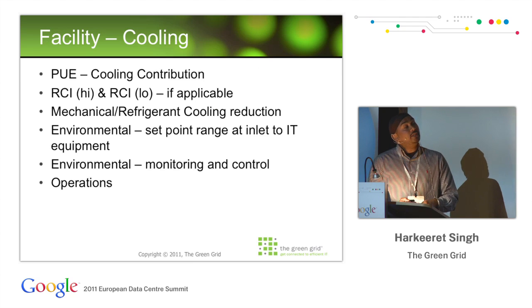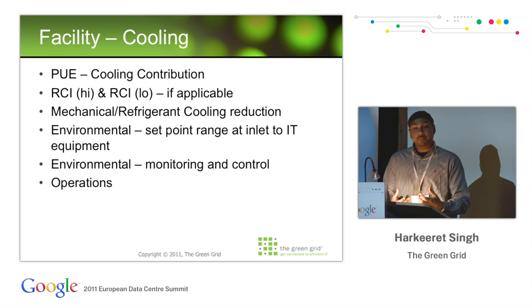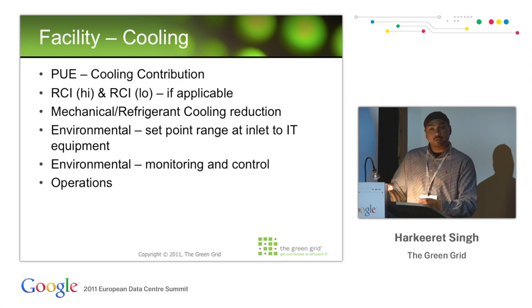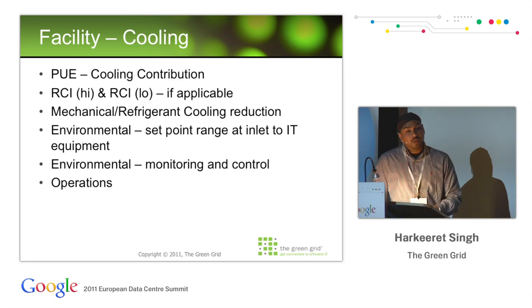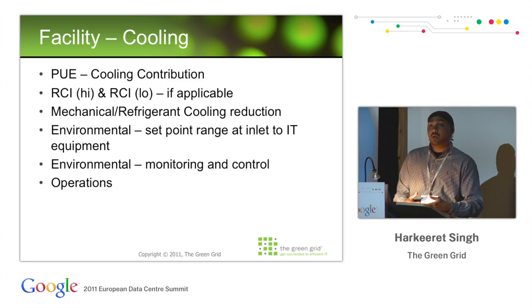Moving over to the cooling side, what we look at is the cooling contribution to your PUE, and as you go further up the levels, that should get smaller. We then look at RCI, the rack cooling index, which looks at how normalized the temperature is of the air going into your servers, and whether that's within the range you want. That's if applicable, because it only applies if you're using air cooling.